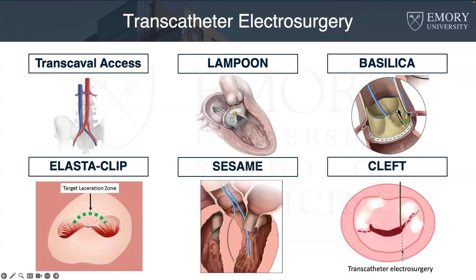And before I go into the details of each procedure, I'd like to review the basic physics of electrosurgery to understand the mechanism of how it works, but also to understand the safety of the procedure. So electrosurgery refers to a delivery of radiofrequency range alternating current, which is very fast, about 500 kilohertz, to cut the target tissue. And this is most commonly used during surgery when surgeons use a handheld active electrode, which is usually the Bovie pencil, to cut or coagulate the tissue.